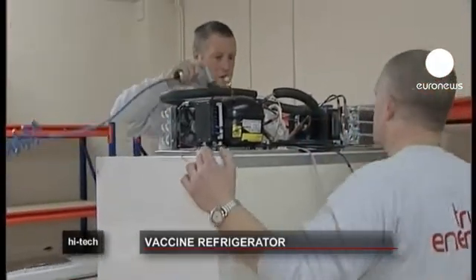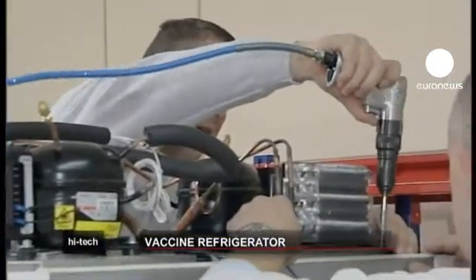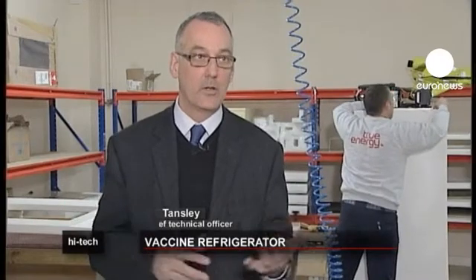It utilizes high-density polyurethane foam insulation and an innovative material to store its energy, which it draws from different sources. The vaccine refrigerator will take energy at any time whenever it's available — from solar power during the daylight hours, and from mains power for just a few hours each day.